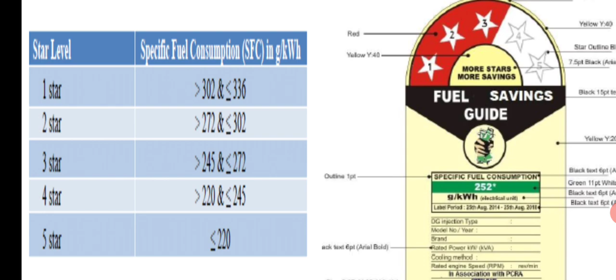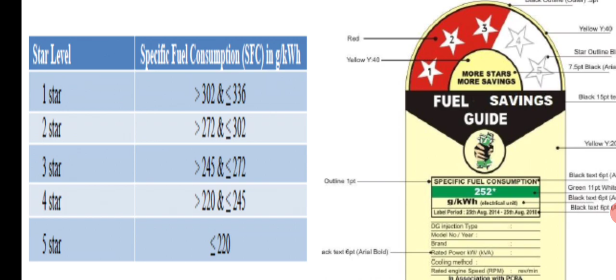One example is a DG set, you just see this DG set. This is a star labeling, how the label is put on the equipment. This is a 3-star rated product. As a mechanical engineer, I think you know about SFC, specific fuel consumption. If a single star rated DG set is there, it may consume around 300 to 336 grams of fuel per kilowatt hour, which means per unit, 300 to 335 grams of fuel. But 5-star rated products consume less than 220 grams.